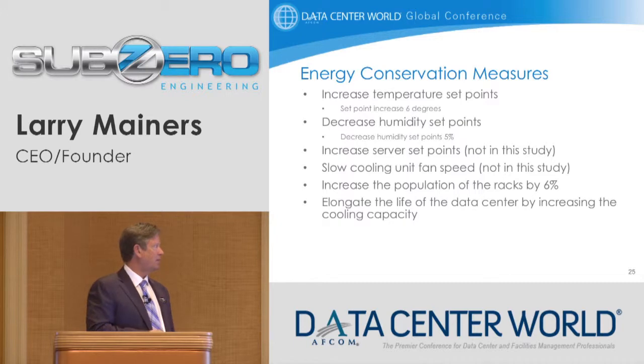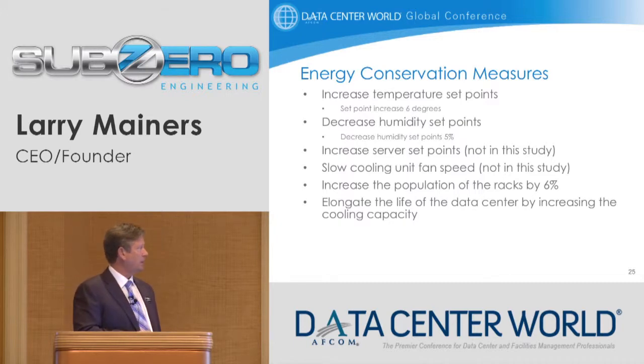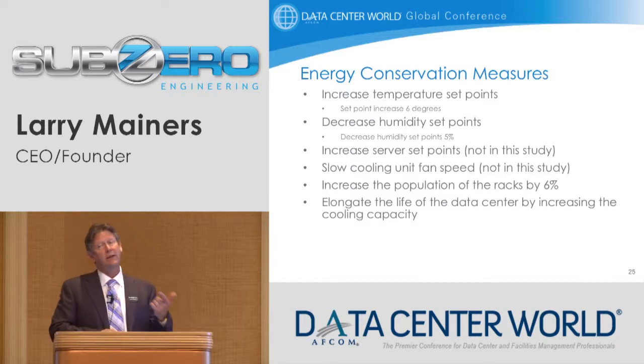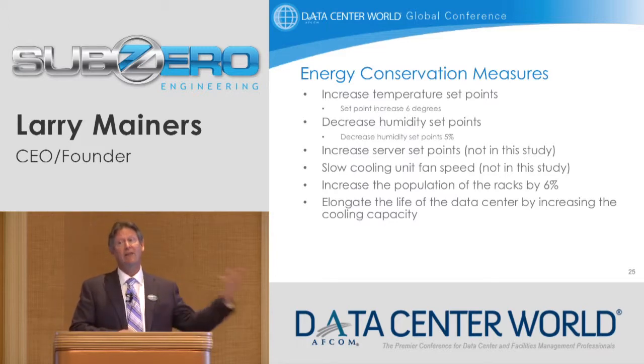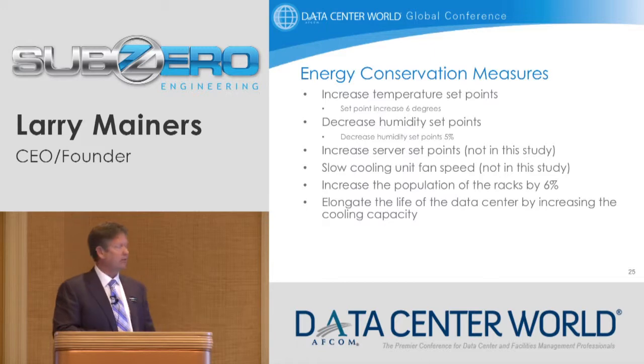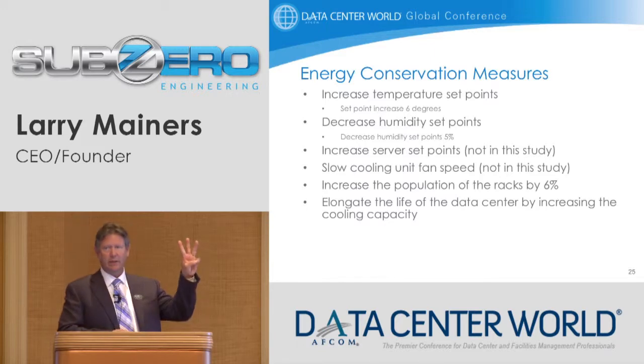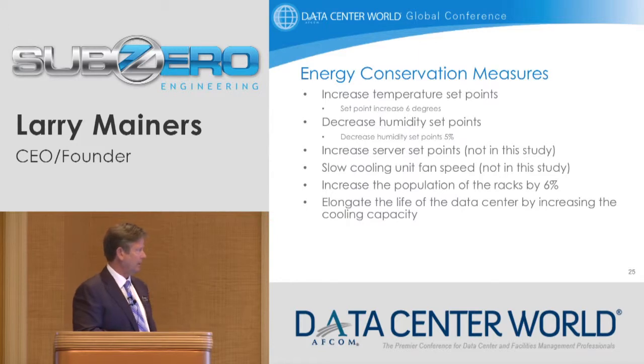Increase temperature set points, decrease humidity set points. Did you guys ever put variable speed fans in your CRAC units? No, they didn't do that yet. And with the rebate, you could even go back later and add variable speed fans. That's a third thing you can change to save energy, and even go back for an additional rebate.